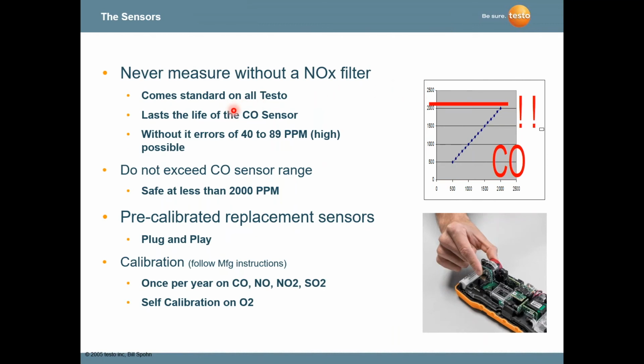CO measurements are very accurate. We measure down to 1, 2, 5 ppm, and we maintain that by calibrating once a year. Your carbon monoxide sensor needs to be calibrated. These sensors are very sensitive down to 5, 10, 15 parts per million, but if you overrange the sensor, in our case over 4,000 parts per million, you could actually damage it. It's not designed to see 4,000 ppm and above. In most cases you can adjust the instrument to shut off when it sees 2,000 ppm.